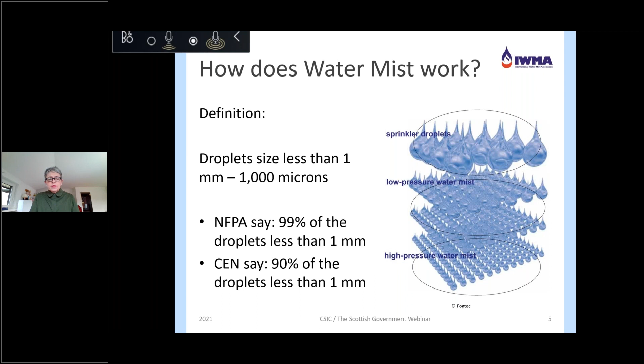However, the droplets ideally need a fire of a certain size. Fact is that water mist systems may have a bit of an issue with small fires because these fires do not have the force or the strength to evaporate the droplets, but still the system will keep the fire in check until the fire brigade arrives.